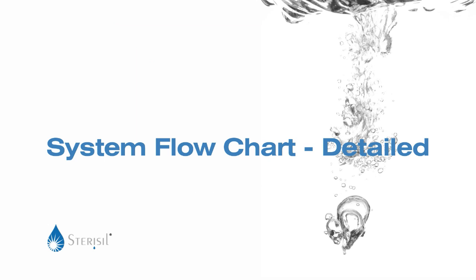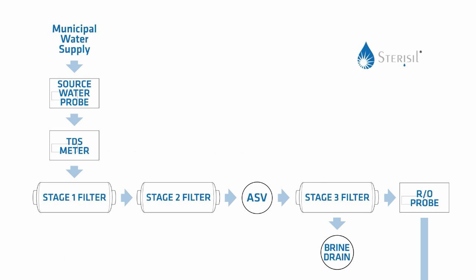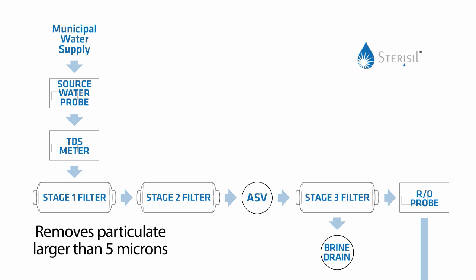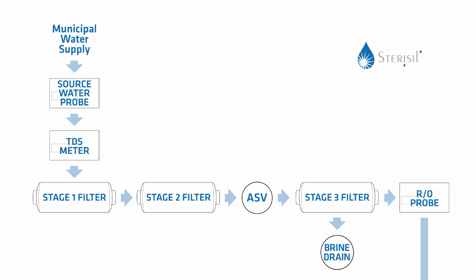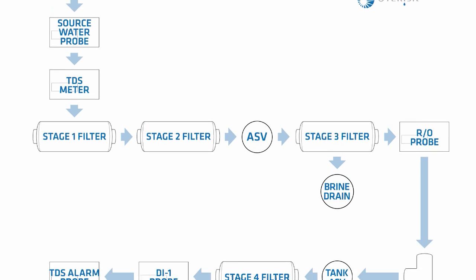Finally, let's take a more detailed look at the sections of the Sterisil system. The source water enters the system and passes the source water probe to determine the water hardness in parts per million total dissolved solids. From there, it flows through the Stage 1 filter to remove particulate larger than 5 microns. The Stage 2 filter removes chlorine. The water then flows through the ASV or automatic shutoff valve, which manages flow through the system. When a cartridge is removed, the ASV closes and flow through the system stops.